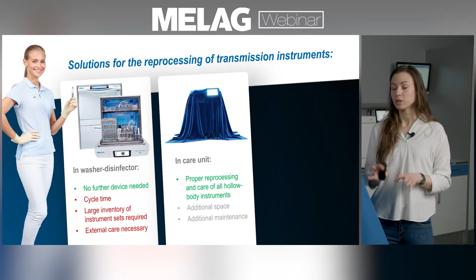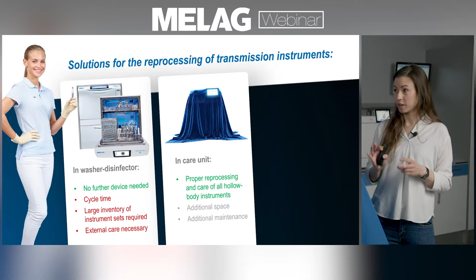You can also reprocess your instruments in care units. That means you have a specific smaller device, for example, for a very fast reprocessing only for handpieces, and also, let's call them, hollow body instruments. They get reprocessed in this device, and then maybe you also have a solution integrated that oils the instruments as well. This is of course then a separate device that you have in your reprocessing room, therefore you need the space. And of course with an additional device you have extra maintenance to do for the device itself.